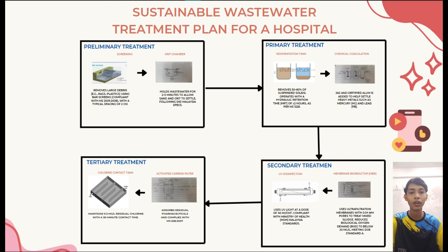Fourth, tertiary treatment. This is the final stage to ensure high quality treated water. Activated carbon filter. This filter removes pharmaceutical residues and other pollutants, following MS 628:2007. Chlorine contact tank. Chlorine is added and the water is held for 30 minutes to maintain 0.3 mg per liter chlorine residual for final disinfection. Thank you, that's all for me.